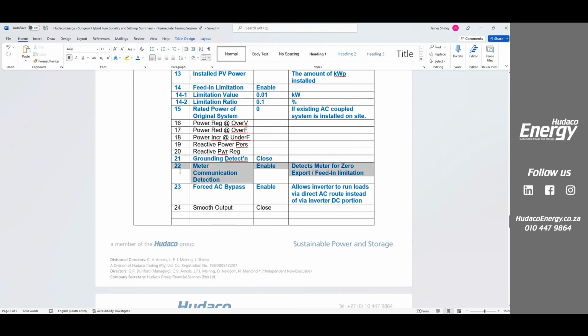Meter communication detection. This is where we would communicate with the CT or with the meter that we provide. And that's what we use to detect for zero export. If you turn that off, the system will stop exporting on the grid port. The moment you turn that off, it'll stop exporting and it will act really just only as a backup system. So make sure that you enable that if you want to be able to run your non-essential loads.